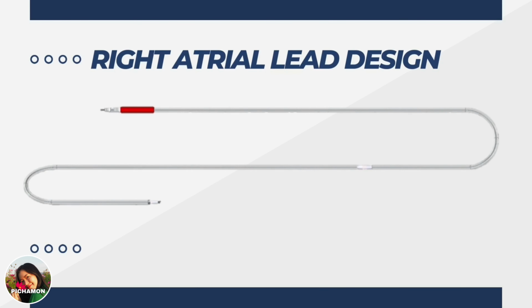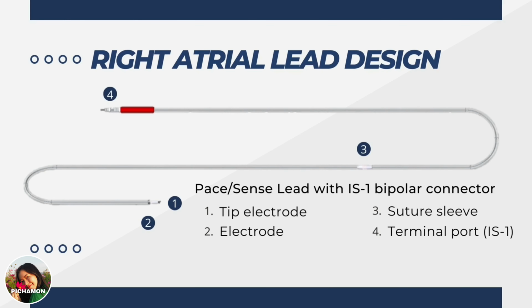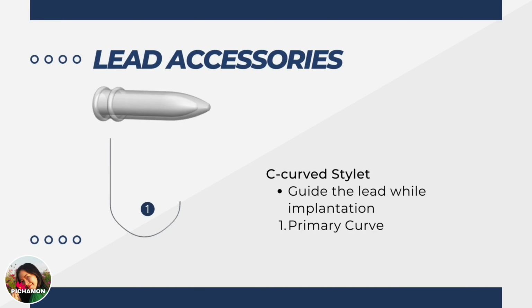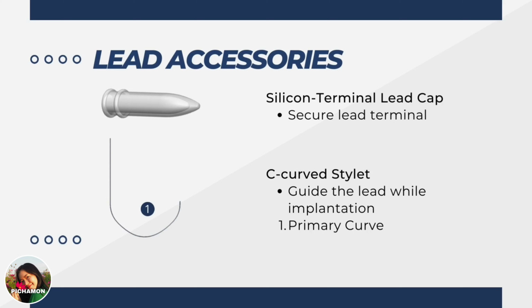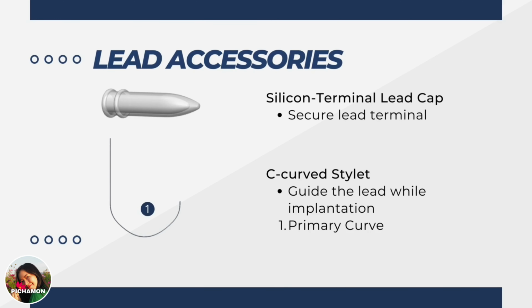The design of the right atrial lead is based on a pacing lead with IS1 bipolar connector. The cathode of this lead is located in the tip electrode and another electrode acts as anode. The fixation helix is located at the tip electrode for fixing the lead. The suture sleeve is used to immobilize and secure the lead in a desired site. For lead accessory, the first one is a silicone terminal lead cap that is used to secure the lead terminal. Another accessory is a C-curve stylet that is used to guide the lead.